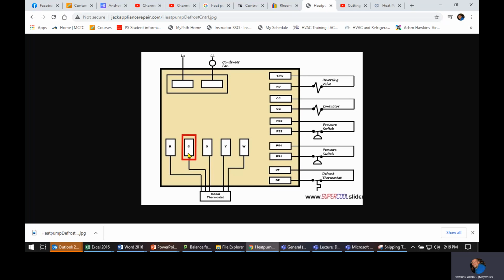So if you're using blue for the reversing valve, in the case of when I hook up my Rheems or Ruuds, I'm hooking up blue to O/B, O or B. So I can't use blue for common. Most of the Ruuds or Rheems use brown as common. So just keep that in mind. Don't assume that blue is always common, brown is always emergency heat or whatever, because in those they use brown for common and blue for the reversing valve. So anyway, you got your reversing valve wire.